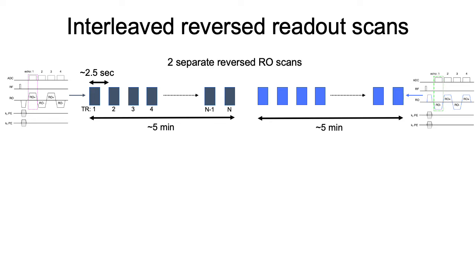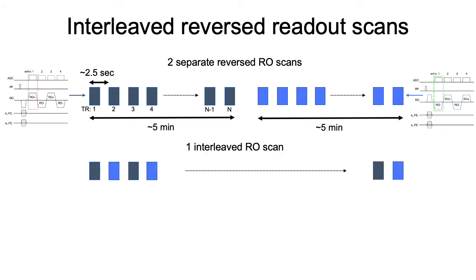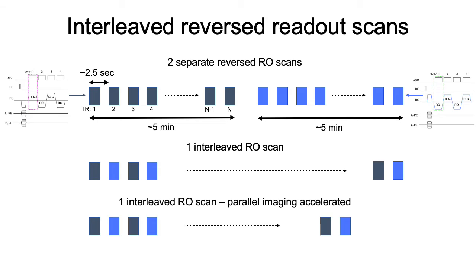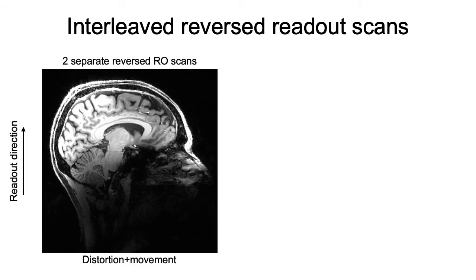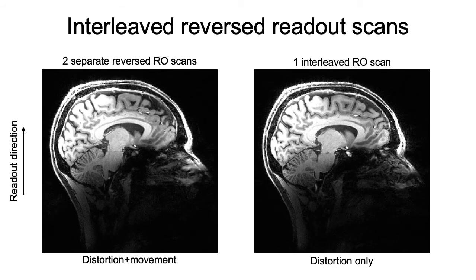We do this in two separate reverse readout scans, or we can acquire one scan with interleaved readout polarity and accelerate that with parallel imaging. In general there will be some movement between two separate scans, making it hard to visualize the distortion between the two reverse polarity acquisitions because of head movement. In the interleaved readout scan you can clearly see the distortion only, without the movement confound.